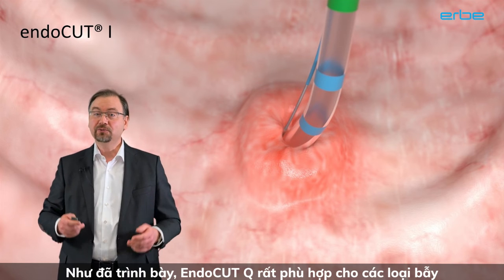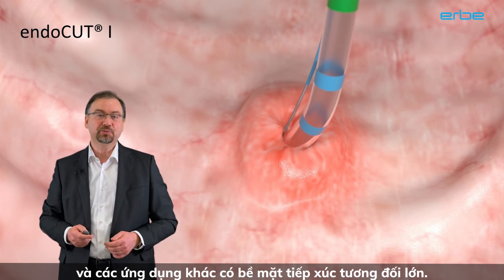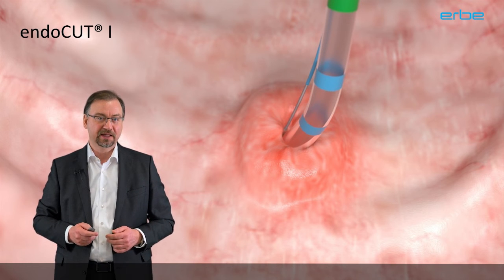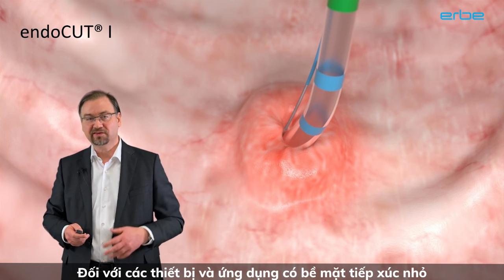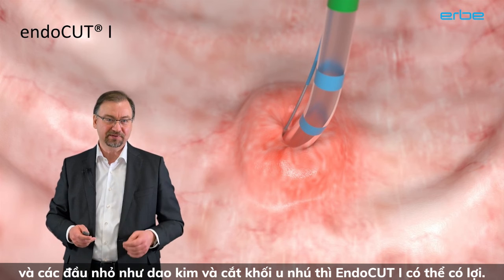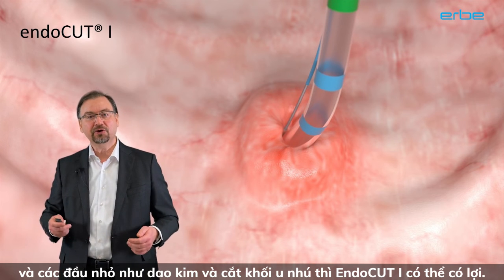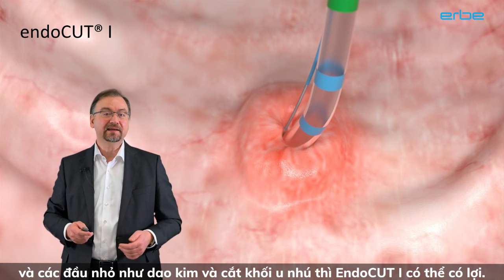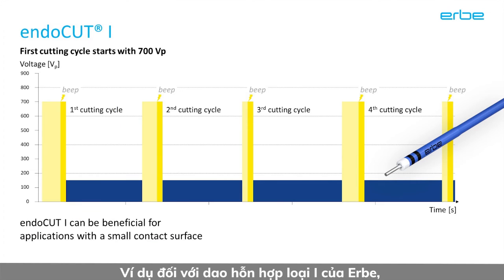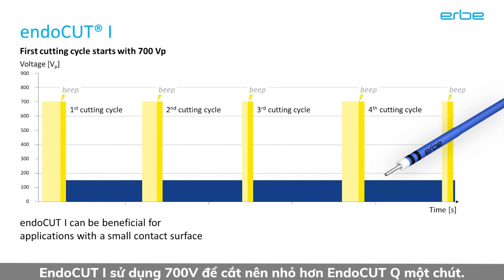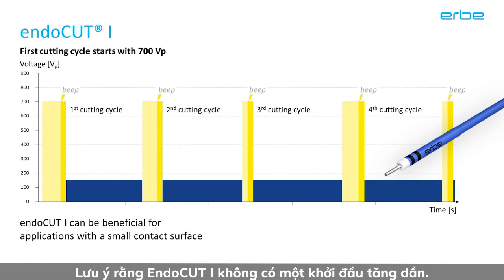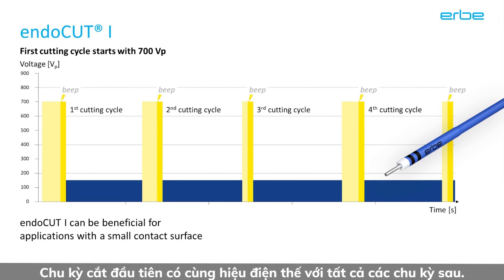As shown, EndoCut Q is great for snares and other applications with relatively large contact surface. For instruments and applications with small contact surface and small tips, such as a needle knife and papillotomes, the other variant, EndoCut I, can be beneficial. For instance, for the Erbe hybrid knife I-type. EndoCut I uses 700 volts for cutting, so a little less than EndoCut Q. Also note that EndoCut I does not have an incremental start. The first cut cycle has the same voltage as all the following cycles.